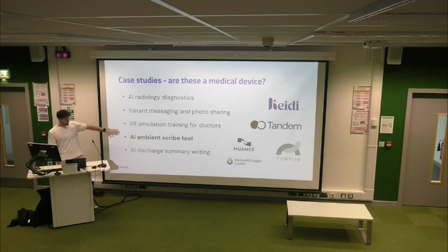The scribe tools are a challenging one because they market themselves as an administrative tool, so they're saving clinicians time, but they're not doing any diagnostic step because they wouldn't, after the consultation, suggest a diagnosis. They'd only report a diagnosis if it was said in the consultation. And that's why they've been operating without needing to be certified as a medical device for over a year now. I can see the arguments either way, but because of the way they're being used in a clinical setting, with a high-level function of summarization by a large language model and the risk of important data either being missed or incorrectly added through hallucinations, they are now expected to be classified as at least a Class 1 device.